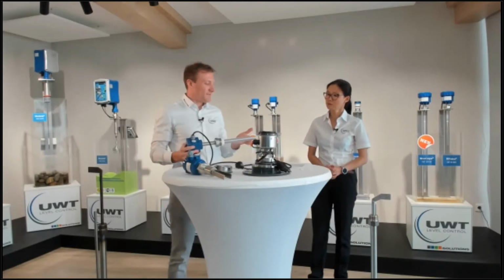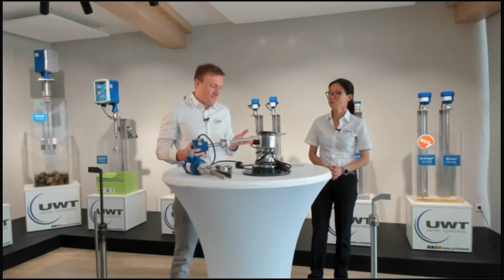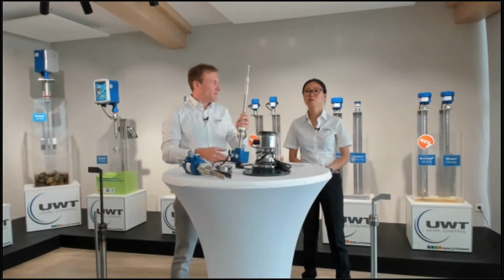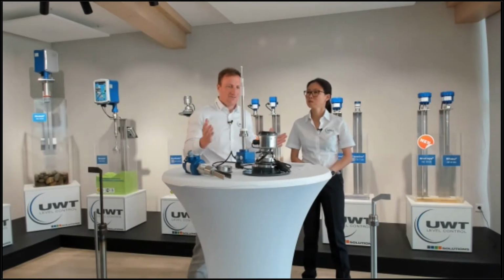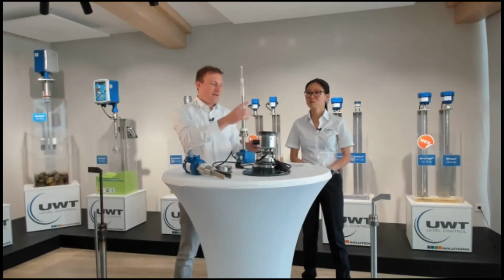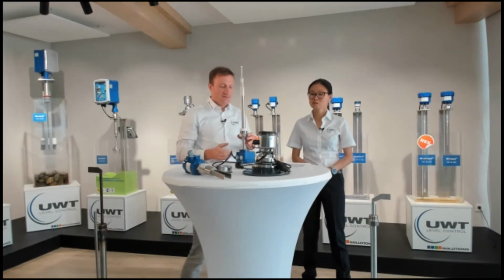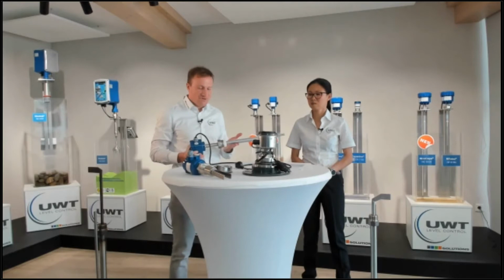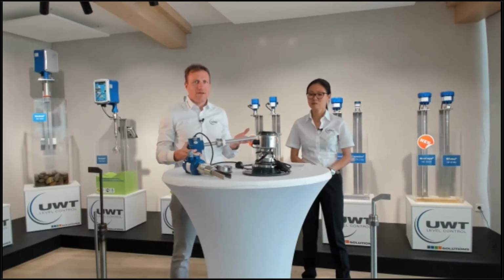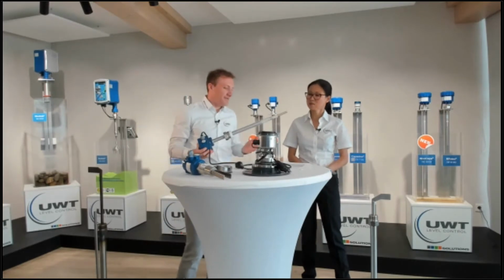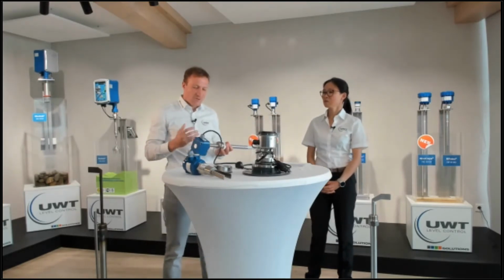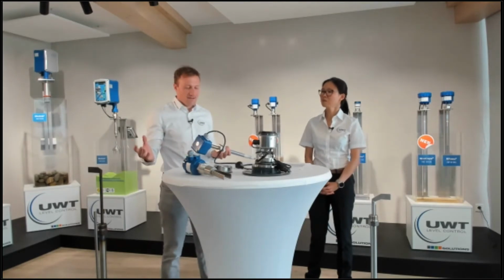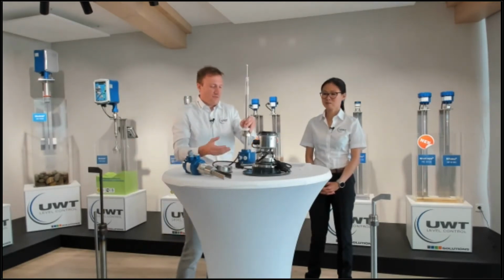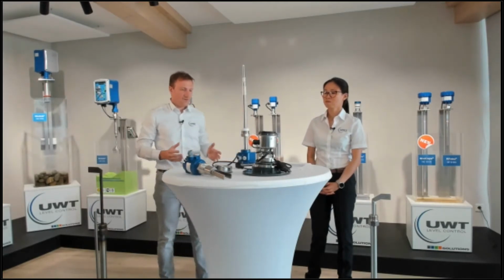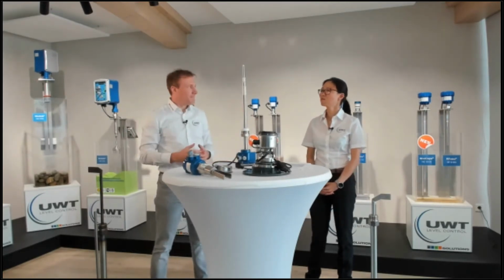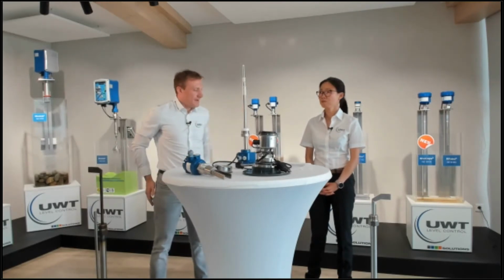It's very resistant due to the coating, and this is important for the corrosive media we have in the ESP filter. We have an active shield technology, so we can ignore buildup around the probe; it has no influence on the measuring result. We also have the option of a remote housing. When we have vibrations in the process, we can use a remote housing where the electronics are located, and then you will get no damage due to the vibrating of the vessel, the tank, the silo or the filter, because the electronics are remote and protected there.